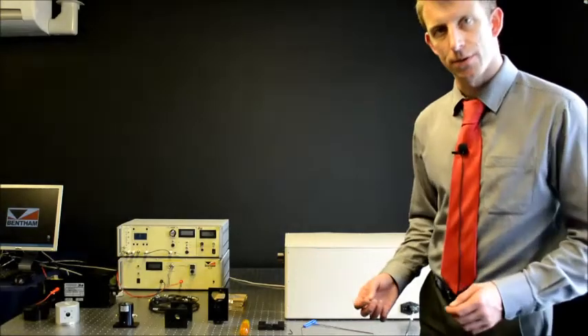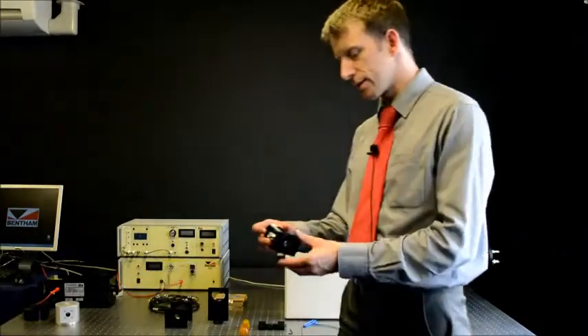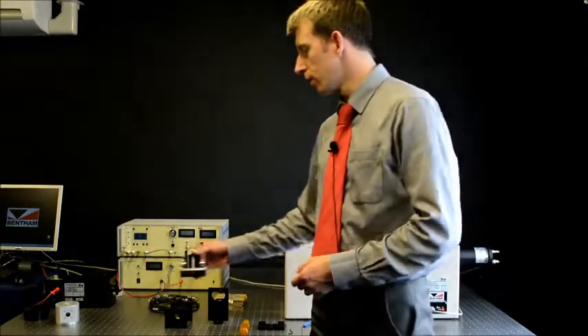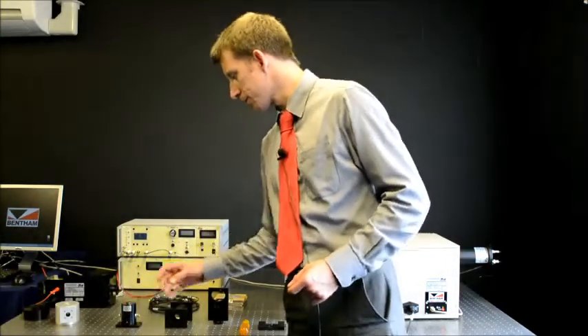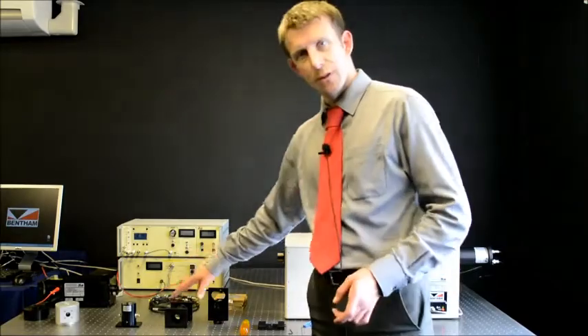To perform measurements in the infrared, that is to say from 1000 to 3000 nanometers, we need to change a few aspects of the IDR300. We need a different detector, the lead sulfide detector in lieu of the InGaAs detector. We need a different input optic, and we need AC detection electronics instead of the detection electronics housed within the IDR300.